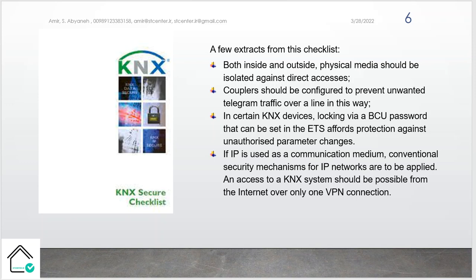If you have devices outside of the building, try to put them on another line with a coupler. For example, a weather station on a roof is better placed on a different line with a new line coupler, because if somebody penetrates the system, they cannot read the data, as the coupler blocks the physical and group address as a target or destination in the packet of data.